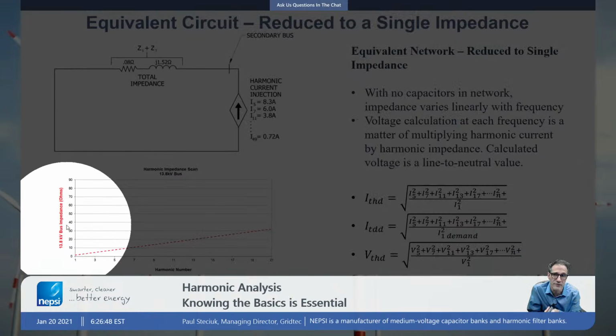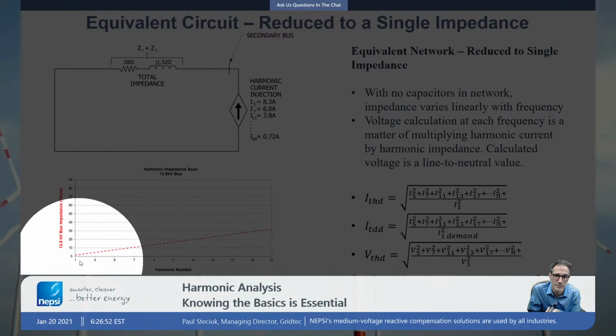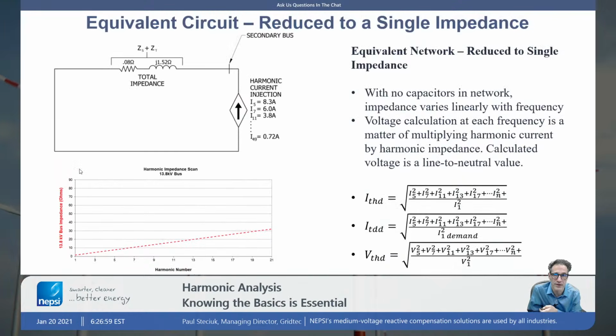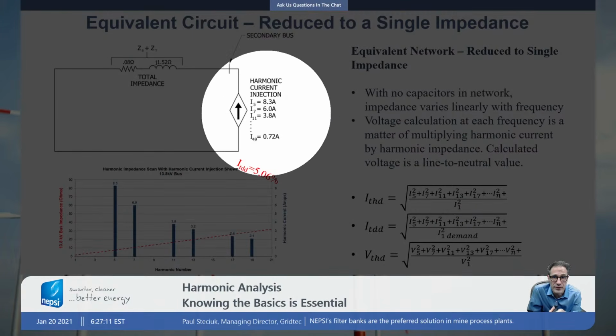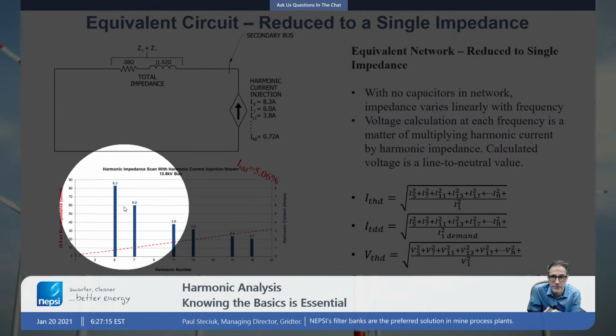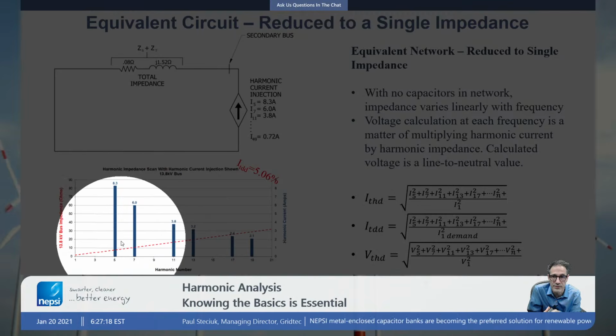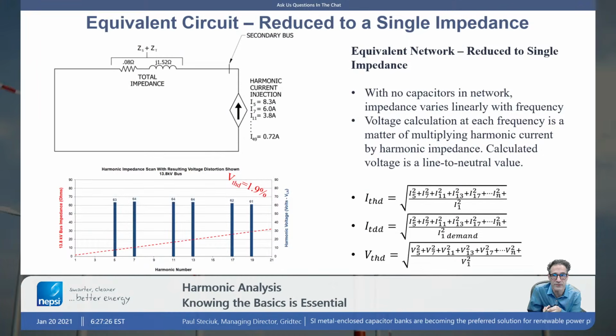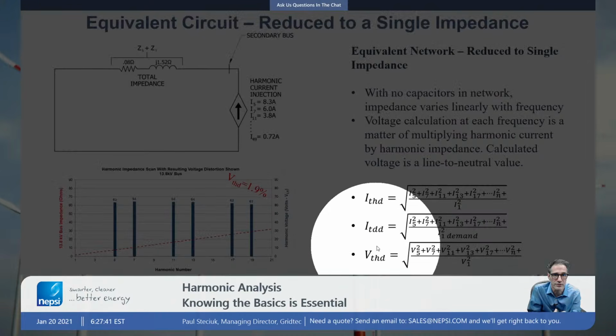So we get a simple straight line for this circuit, just a simple straight line. As we go up in harmonic number, we go up linearly in ohms with harmonic number or with frequency. We can take the values of 8.3 amps here and overlay onto this impedance curve here. So 8.3 amps times that value of ohms at the fifth harmonic, okay, will give me the volts. And that's what I do here. I can do that at each and every frequency, and I create a bar chart. VTHD is, in this case, 1.9%, calculated according to the equation here.